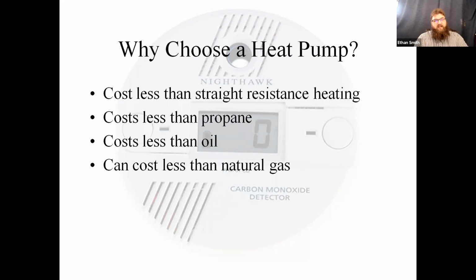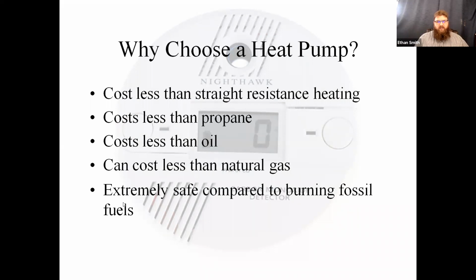I did them last year for my system, and I have kind of a unique situation. My heat pump is more financially efficient, in terms of dollars per therm, when the temperature outside is above 35 degrees. Below that temperature, it's more efficient financially to run my natural gas furnace. So I have the controls set up with what's called an economic balance point, and I'll show you how to do that in a little bit here, guys. Natural gas right now in this country is pretty cheap in most places, so it could be a toss-up. It could be blanket-statement cheaper to run natural gas, or it could be cheaper to run your heat pump. It just depends, so I encourage you guys to do that on your own.